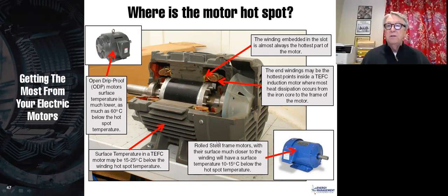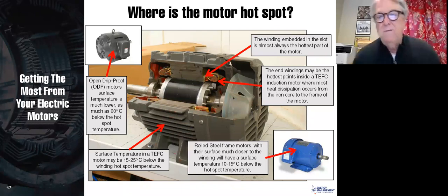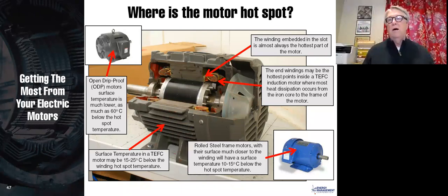If you have a rolled steel frame motor, that's a little better because the rolled steel is in contact with the iron, and therefore the temperature on the outside of the motor is 10 to 15 degrees below the hotspot temperature. I'm going to use TEFC because I love those, and those are the standard of industry. The surface temperature in a TEFC motor is approximately 15 to 25 degrees centigrade below the winding hotspot.